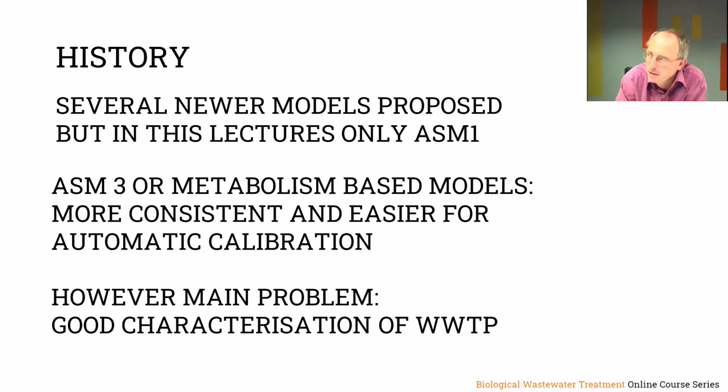The main problem in modeling is also, and that I would like to emphasize really, that it's much more difficult to get good data from a wastewater treatment plant than getting good model parameters. People focus quite easily on all the model parameters, the Ks, the mu max, the yield coefficients. But getting the correct recirculation flow rate, or the correct recycle flow rate, is often very difficult to do, and often a 10% deviation in that flow rate has a much bigger impact on the model outcome than a 10% variation in the maximum growth rate. So the difficulty is the characterization of wastewater treatment plants.